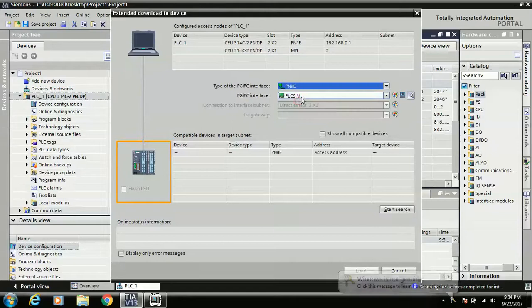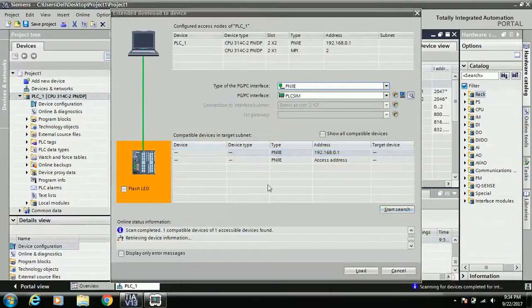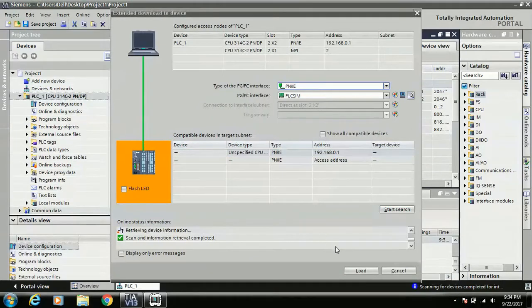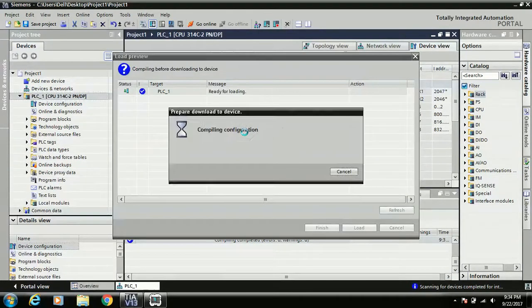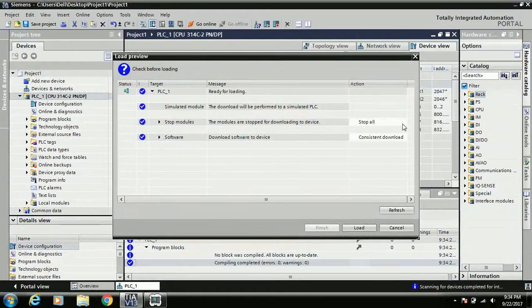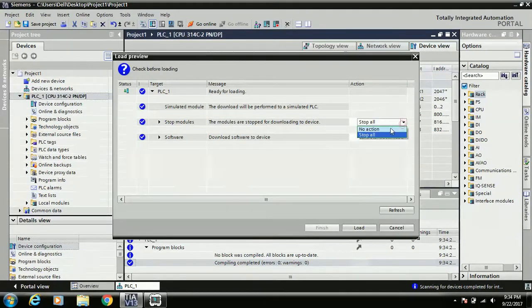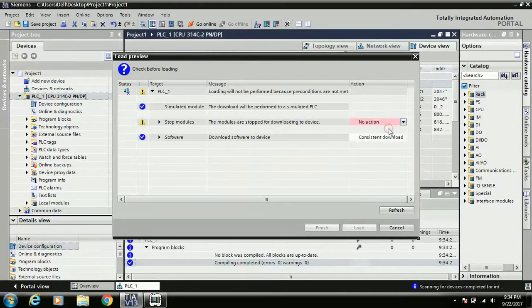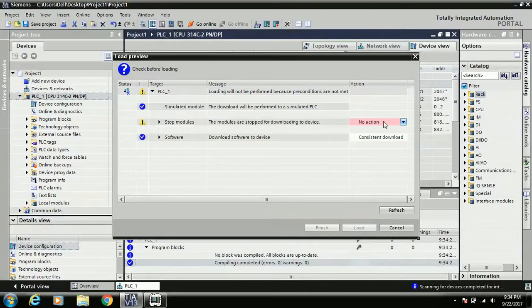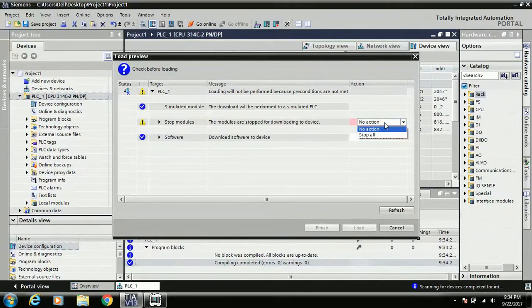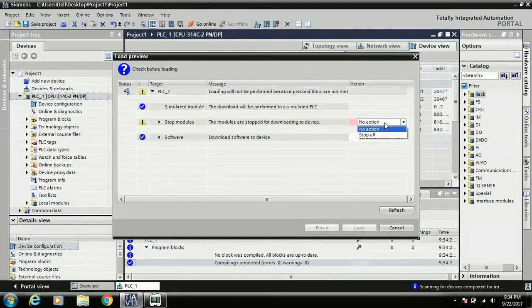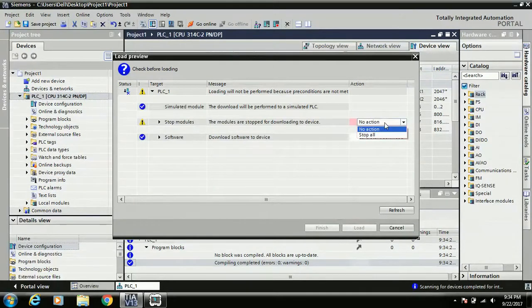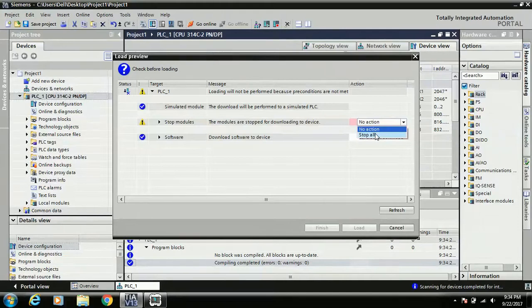Again, first search the download medium drivers and give the start search and load. Now it is compulsory to stop the module, because here you set no action means it is not working. When you just click on the PLC and try to download, your system data is also updated. If your system data is downloaded to your PLC hardware, at that same time your PLC could not execute any program - for this reason we always set it in stop mode.